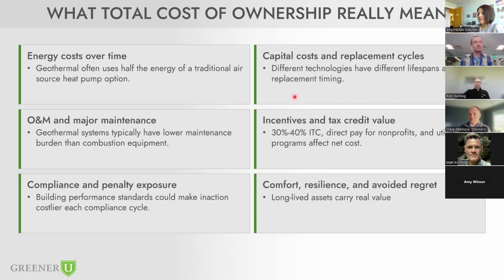The other big one to consider is capital replacement cycles. In a recent example, the less expensive air source option was a one-for-one replacement of rooftop units that had cooling on them and were gas fired, and we said, we're going to go to a heat pump version. Well, an air source heat pump RTU is a great option, but it's going to have a shorter life. Generally, we're seeing those start to see increased maintenance and failure right around 15 years or so. The ones that are getting closer to 20 years are really end of life. Especially here in New England, the compressors on those cooling systems and heat pumps are going to be exposed to the elements year round. With New England winters, you're not going to get the same life out of those.